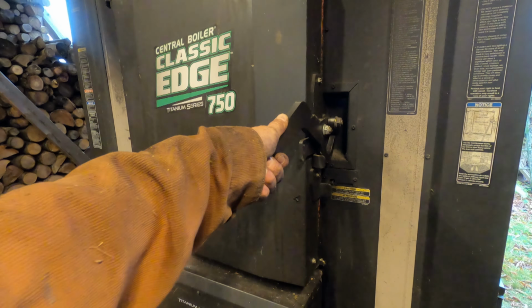I'll go around to the other side and we'll talk about the pressurized boiler portion of it. This is actually unpressurized. It's just atmospheric pressure. So this is the pressurized side. You can see the stainless steel flexible pipes there, also 1.25 inches. So this runs, you know, typical home hot water baseboard heating, runs about 15 psi. But what I do is it is connected to the infeed side, so all these zones here feed in this way, and right now I have that valve shut, so that prevents the water from going through the heat exchanger, and this valve open, so it just goes directly into the oil boiler. So then what I do in the wintertime is I open this valve and shut this.